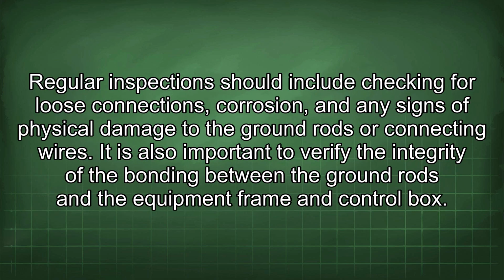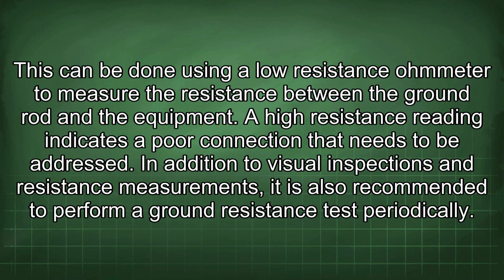Regular inspection should include checking for loose connections, corrosion, and any signs of physical damage to the ground rods or connecting wires. It is also important to verify the integrity of the bonding between the ground rods and the equipment frame and control box. This can be done using a low resistance ohmmeter to measure the resistance between the ground rod and the equipment. A high resistance reading indicates a poor connection that needs to be addressed.